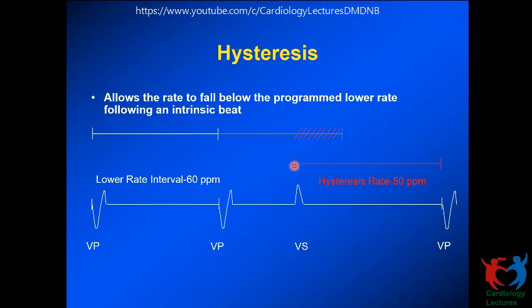Which means effectively you are allowing a rate below the lower rate, which happens to be 55 for this patient. It will continuously allow that. But when the rate drops to as low as 50, it will do one pacing, and from that time onwards, it will pace at a rate of 60 beats per minute. So for that to happen, there should at least be one event faster than the lower rate for hysteresis to kick in. So this will be useful for a patient that has intermittent bradycardia, where you do not want to pace more often, but when you pace, you want to pace at a slightly higher rate.